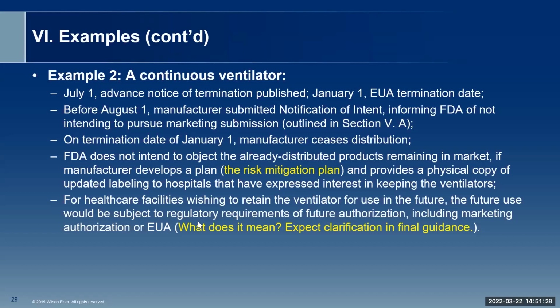The FDA does not intend to object to the already distributed products. They can remain in the market and continue to be used by the end users, provided that you provide a physical copy of updated labeling to the end users and the hospitals. You have to tell them that your product is out of EUA and that you do not intend to continue marketing your product. And in that situation, the FDA says, for healthcare facilities wishing to retain the ventilator for future use, it would be subject to regulatory requirements of future authorization, including marketing authorization or EUA. It really is not that clear what the FDA means to say in this sentence. We expect some clarifications in the final guidance.